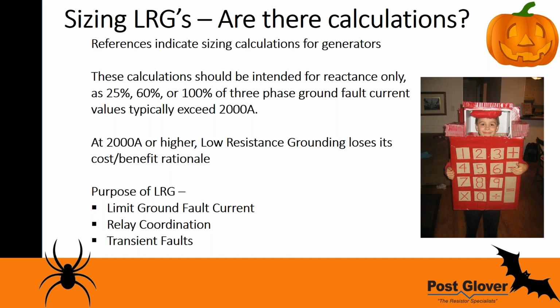There are some references I've found that talk about sizing resistance grounding. In my opinion, they're not really good for this because they're really talking about reactance. A lot of times we want to put these in the same category, which isn't quite right. When talking about protecting generators, you could use both, but if you're looking at exceeding 2,000 amps on an NGR, which is 60% or 100% of your three-phase voltage fault, which is what these calculations refer to, you're going to be above that usually, and that means there's really no question.